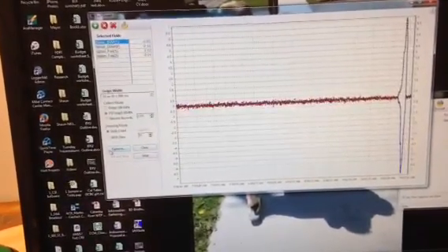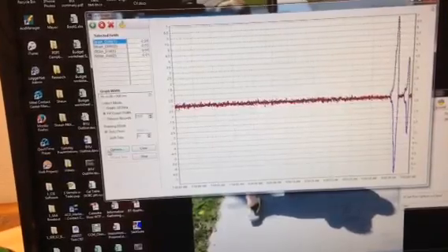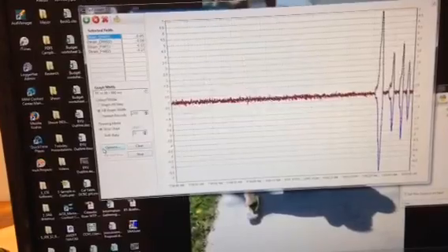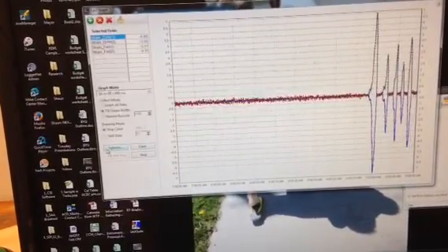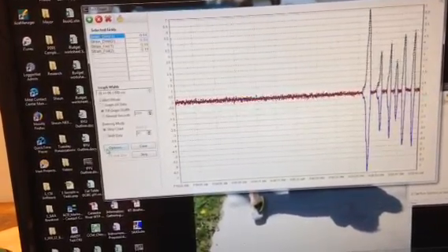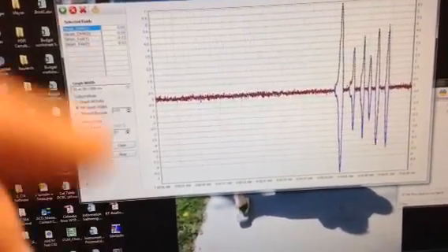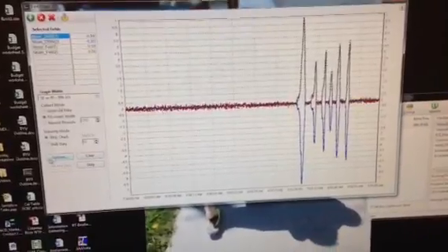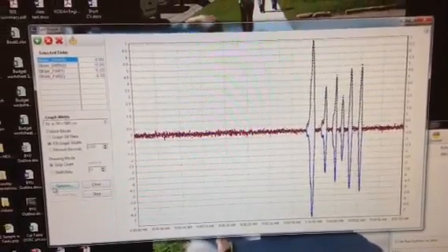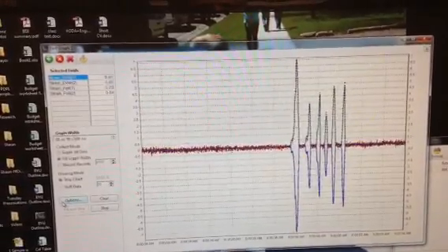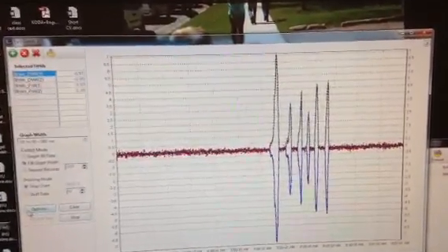When we apply the load so that it scales, now what we see is the sensitivity of the gauges. The solid lines represent the vibrating wire data. The dotted lines represent the bonded foil data. You can also look at that as red and blue. So the red is the bonded foil data, the blue is the vibrating wire data.